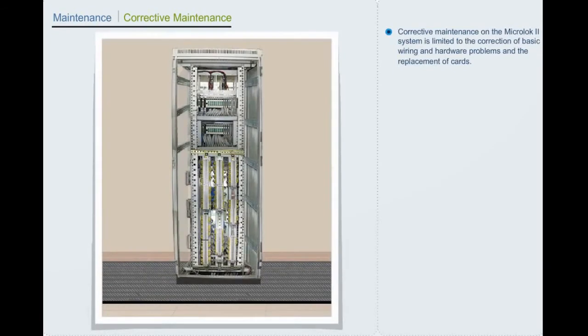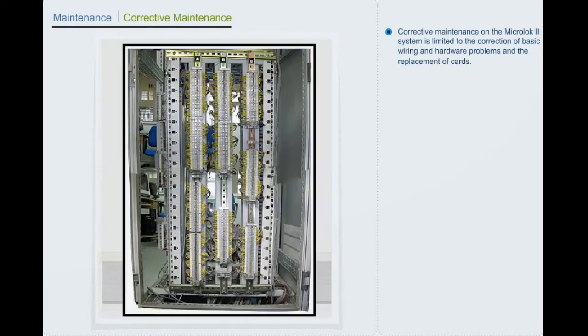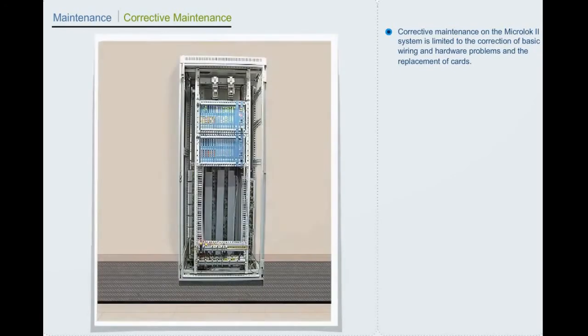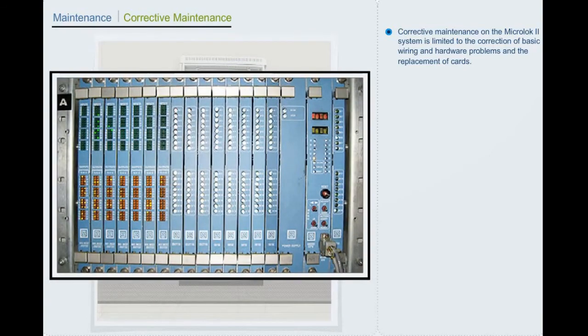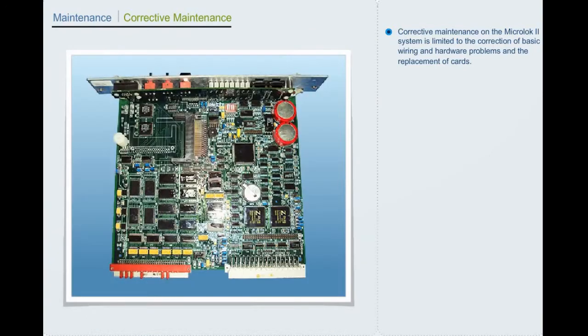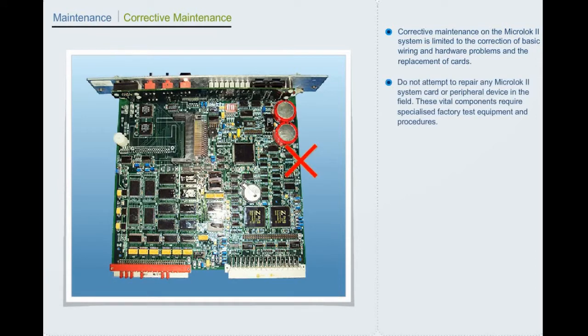Maintenance. Corrective maintenance. Corrective maintenance on the Microlock 2 system is limited to the correction of basic wiring and hardware problems and the replacement of cards. Do not attempt to repair any card or peripheral device of Microlock 2 system in the field. These vital components require specialized factory test equipment and procedures.